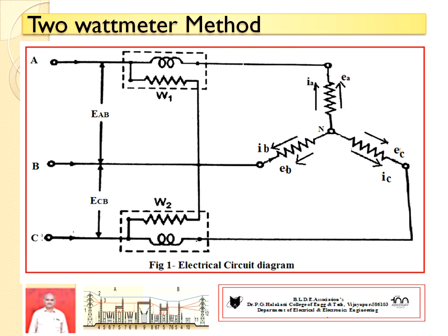There are 2 wattmeters, W1 and W2, in this method. The algebraic sum of these 2 wattmeters, W1 plus W2, gives the total three-phase power. In this method only 2 wattmeters are used, hence it is advantageous. It saves wattmeter connections and avoids the complication of wiring systems. Hence commercially the 2 wattmeter method is more useful in three-phase electrical systems.